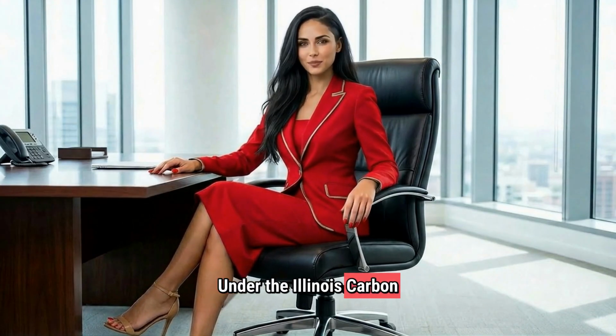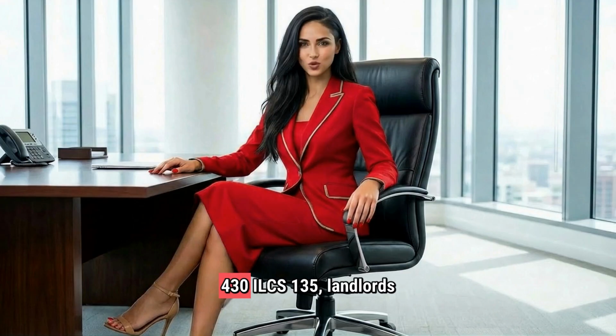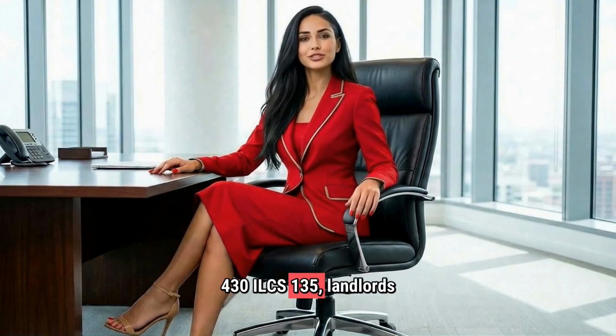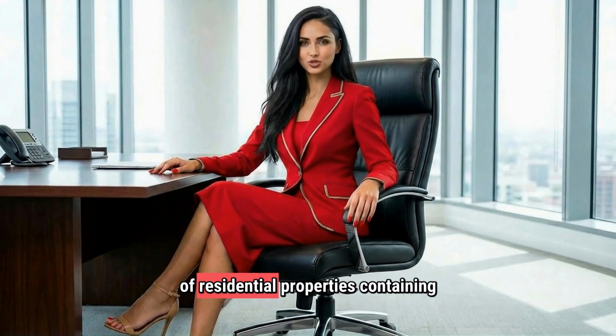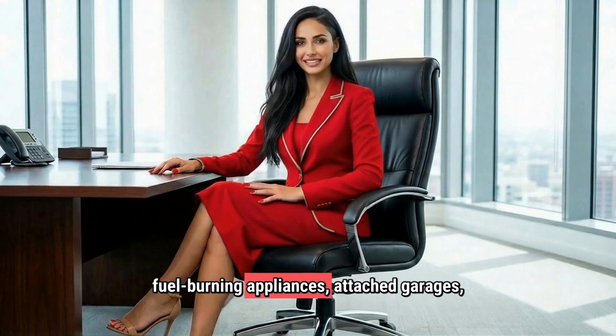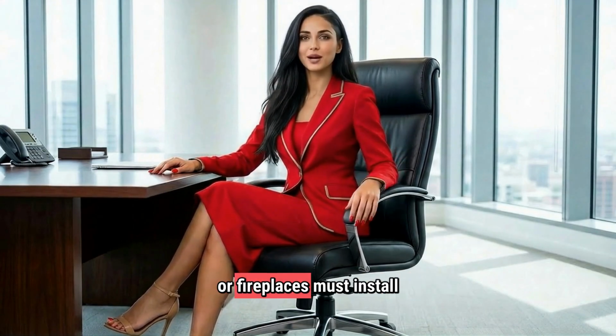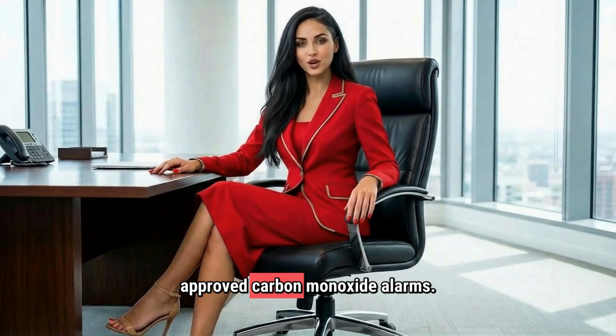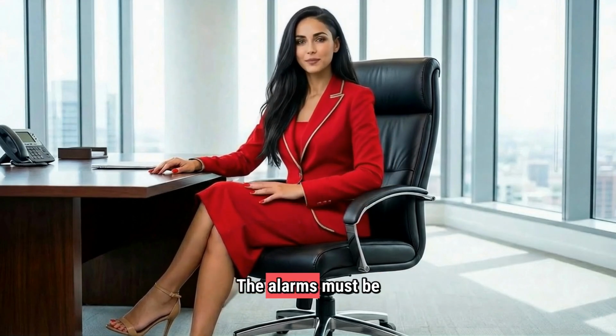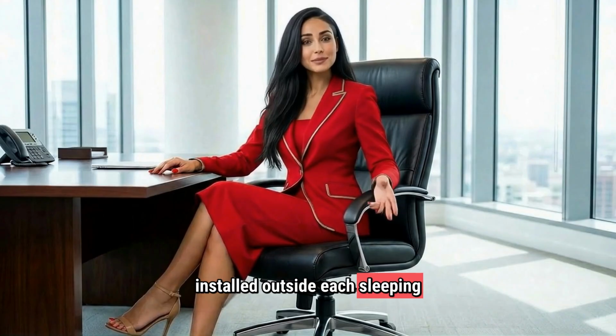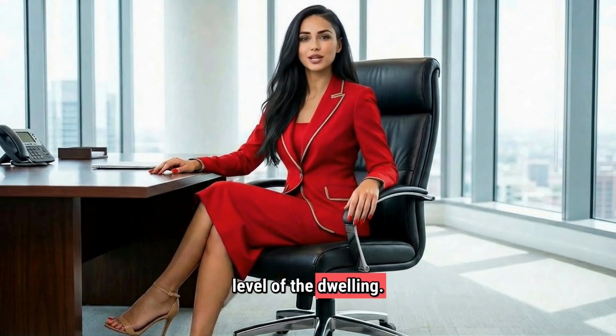Here's what Illinois landlords need to know about carbon monoxide detector requirements. Under the Illinois Carbon Monoxide Alarm Detector Act, 430 ILCS 135, landlords of residential properties containing fuel-burning appliances, attached garages, or fireplaces must install approved carbon monoxide alarms. The alarms must be installed outside each sleeping area and on each level of the dwelling.